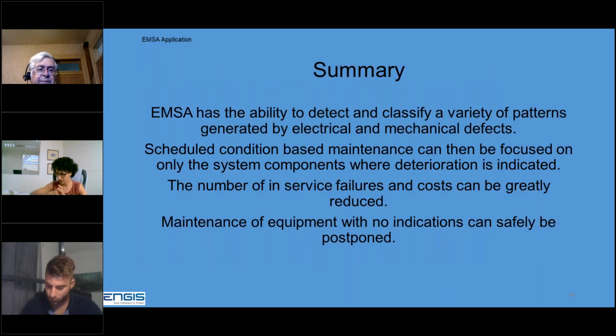So to summarize, EMSA has the ability to detect and classify a variety of problems, both electrical and mechanical defects. You can then schedule condition-based maintenance and focus only on the systems that need maintenance because deterioration is indicated. You can reduce the number of in-service failures. You can greatly reduce your maintenance costs because you'll have an idea of what the problem may be and where to look.